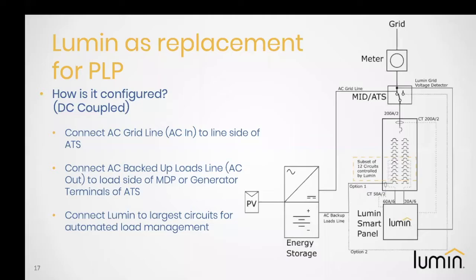This is important for the PV system to be able to both supply load or export in regular grid operation. However, it must be isolated in the event of an outage. So the ATS will effectively do that. Next, the AC out or backed up inverter output can then be connected to either the load side of the main distribution panel through a backfed circuit breaker or the alternate power terminals in the ATS. So you can see, if doing a load side connection, that's located right here, or option 2 follows this up to traditionally the generator terminals in that automatic transfer switch. So those are a couple of different ways that those types of inverters can be connected.